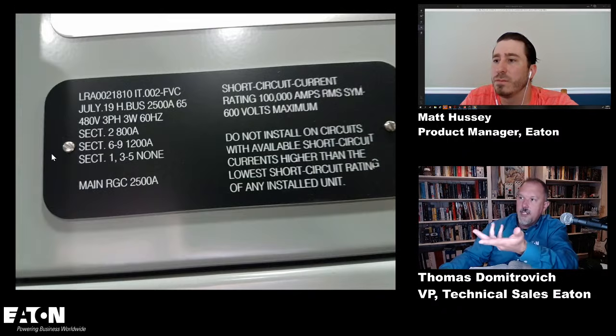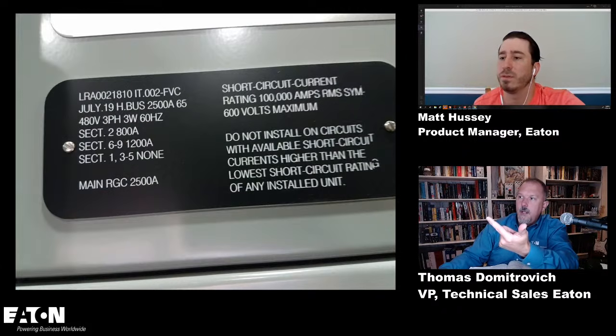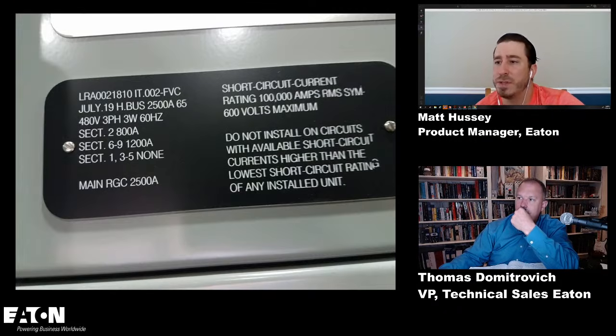I mean, we've got section 2 is 800 amps. Yeah, those are designating the vertical bus ampacities, and then you've got the horizontal bus ampacities mentioned above that. Okay, the horizontal buses. This is a 2500 amp. Yep. What's that 65? 65°C rise off of the horizontal bus. So 40-degree ambient condition. The bus is rated to not have a temperature rise above 65°C. Okay.